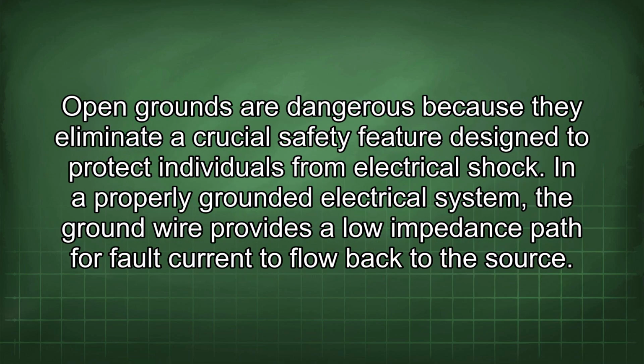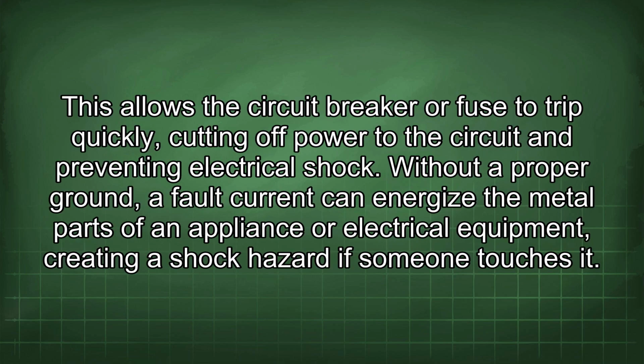Open grounds are dangerous because they eliminate a crucial safety feature designed to protect individuals from electrical shock. In a properly grounded electrical system, the ground wire provides a low impedance path for fault current to flow back to the source. This allows the circuit breaker or fuse to trip quickly, cutting off power to the circuit and preventing electrical shock. Without a proper ground, a fault current can energize the metal parts of an appliance or electrical equipment, creating a shock hazard if someone touches it.